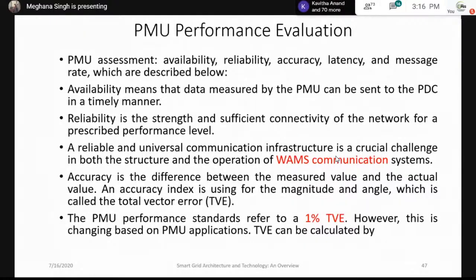Accuracy is the difference between the measured value and the actual value. The accuracy index is given by the magnitude and angle, which is called total vector error. And please understand, total vector error should be less than 1%.